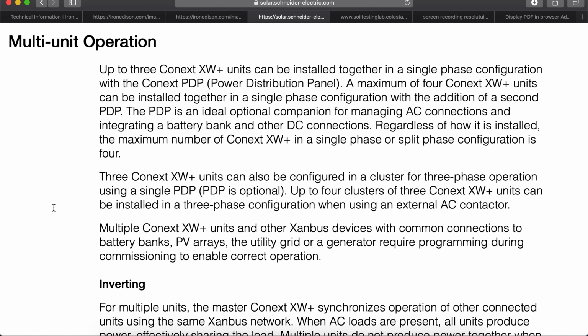Multi-unit operation. Up to 3 Conext XW Plus units can be installed together in a single-phase configuration with the Conext power distribution panel. A maximum of 4 Conext XW Plus units can be installed together in a single-phase configuration with the addition of a second PDP. The PDP is an ideal optional companion for managing AC connections and integrating a battery bank and other DC connections. Regardless of how it is installed, the maximum number of XW Plus in single-phase or split-phase configuration is 4.